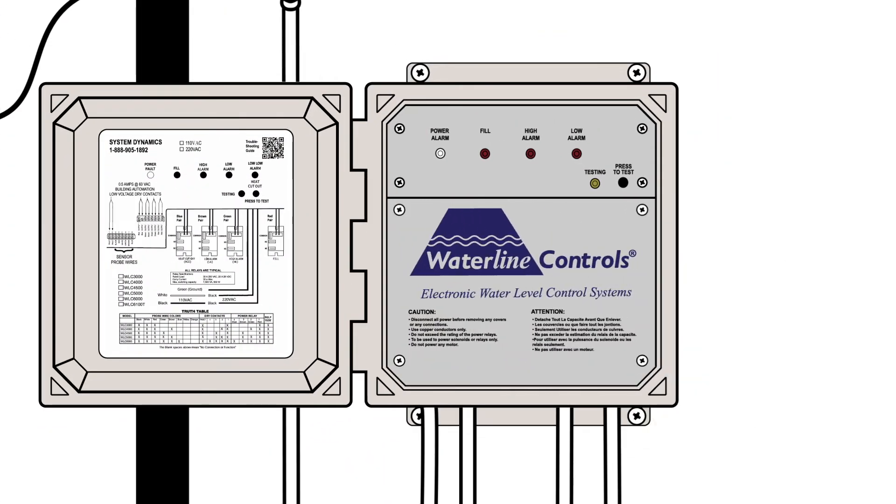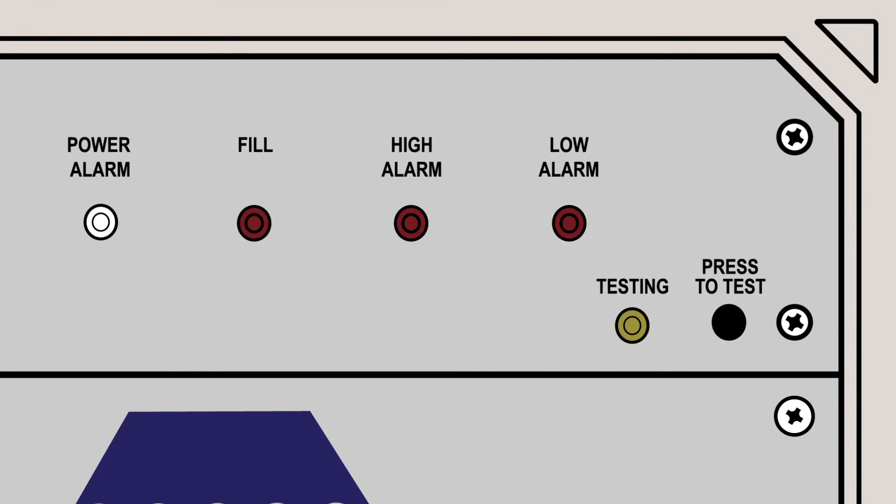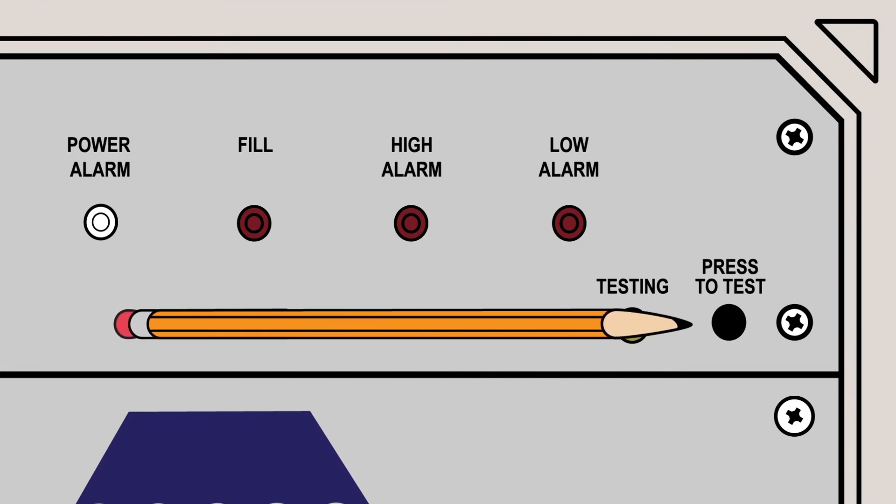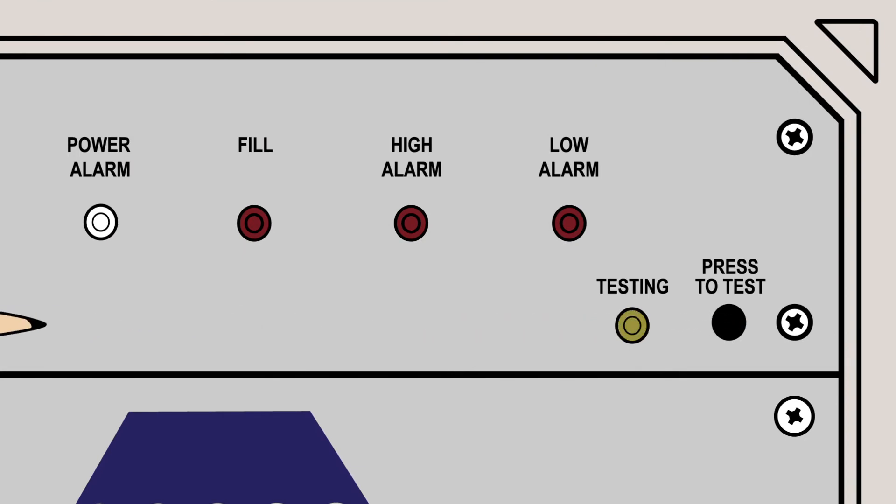To test your waterline control system, press the press to test push button using the tip of a pencil or pen. The yellow testing LED turns on and remains on during the test. Each switch will turn on the LED, the BMS connection, and the high voltage respective relay. Once testing is completed, the power alarm LED will flash five times, turn green, and the yellow test light turns off.